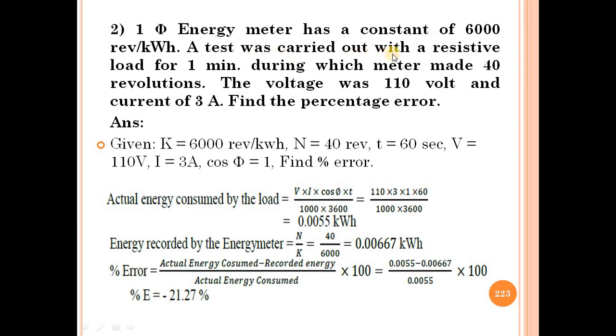A test was carried out with a resistive load for one minute, so time T = 60 seconds. During which the meter made 40 revolutions, so N = 40. The voltage was 110 volt and current was 3 ampere. Power factor is assumed to be 1. We need to find the percentage error. Given: K = 6000 rev/kWh, N = 40, T = 60 seconds, V = 110 volt, I = 3 ampere.